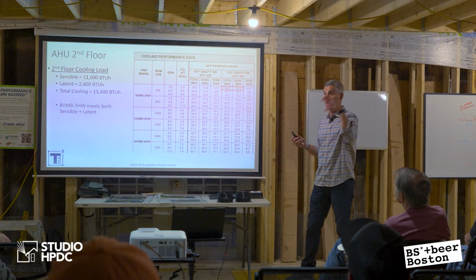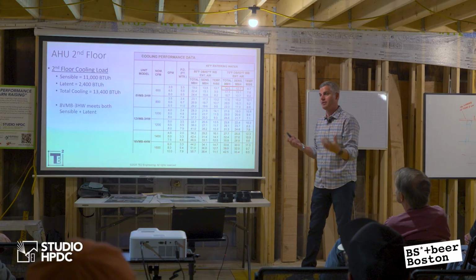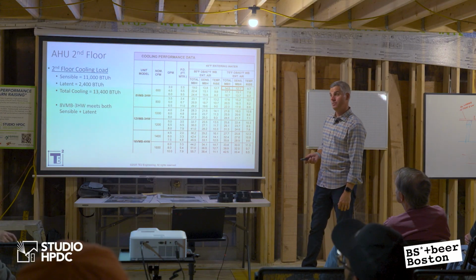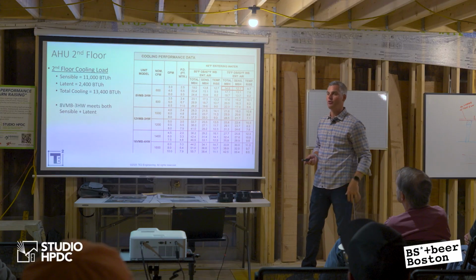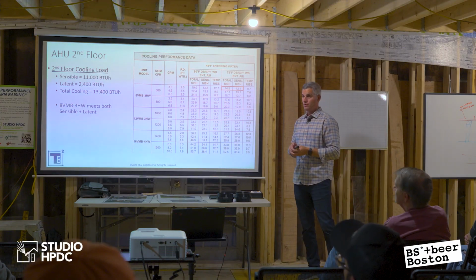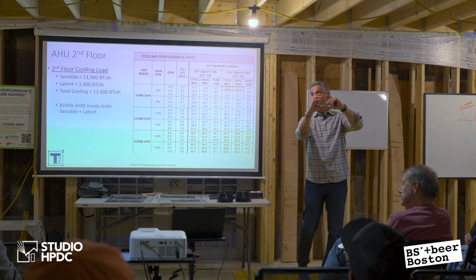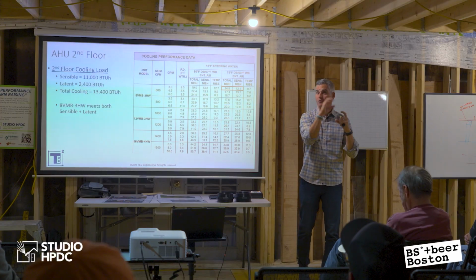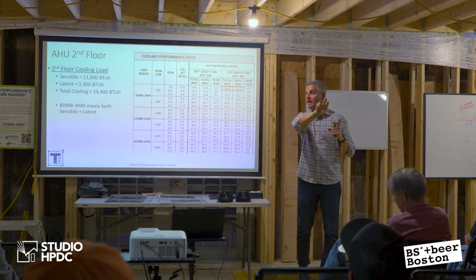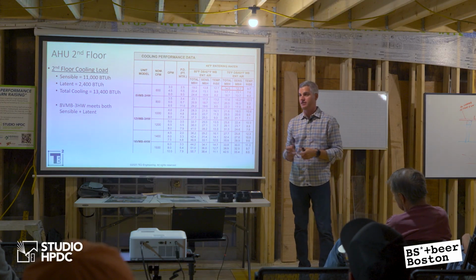Obviously the dehumidification load will be here, which will be picked up by the dehumidifier and controlled by a humidistat in this space. It wouldn't even necessarily have time to get upstairs. So the idea is that the thermostat controls the air handler for heating and cooling, but it also has a dehumidification function that turns on the dehumidifier when it needs to.